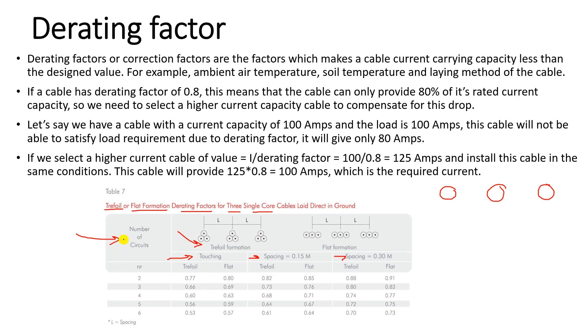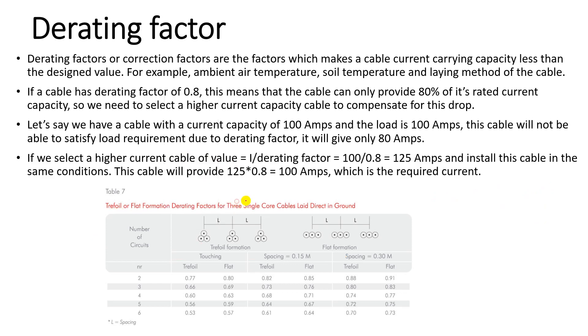The number of circuits refers to how many cable cores are used per phase. For example, if each phase uses two cables, that is two circuits per phase — phase A takes two circuits, phase B two circuits, and phase C two circuits. As shown in the catalog, the more circuits used, the lower the derating factor becomes.